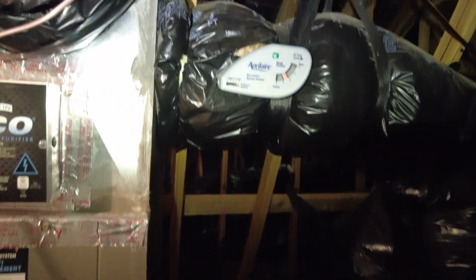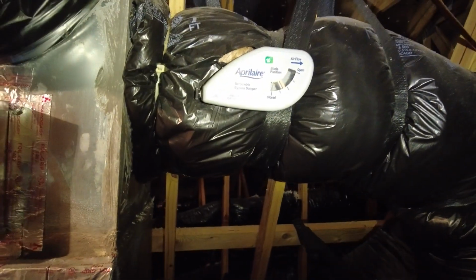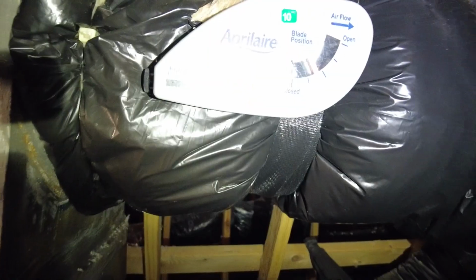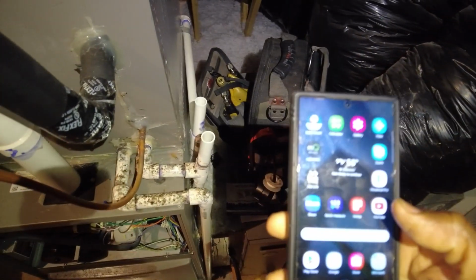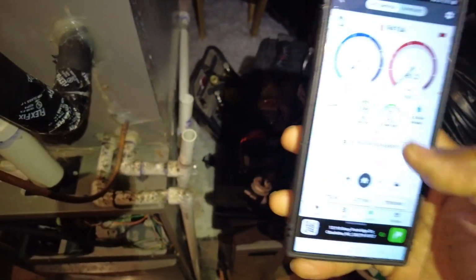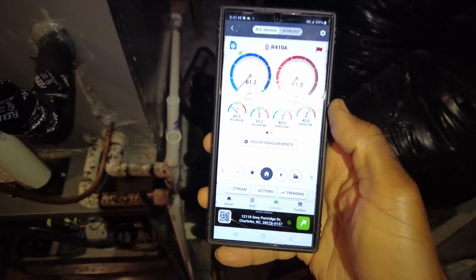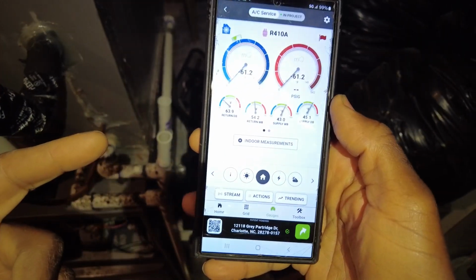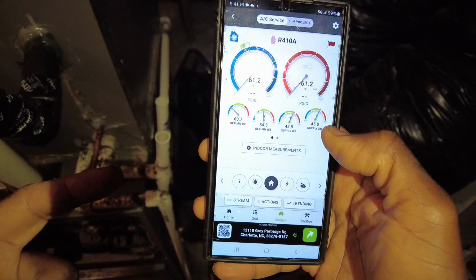First thing I noticed when I walked up in here was this here. You know what that is, and let's see if it's zooming in properly or for too much light. So you see that zone damper is about 50% of the way open, and I've got both zones calling right now. Okay, so if you take a look at our temperature split, look at our return and supply. Return is 63 degrees. Okay, supply is 45.